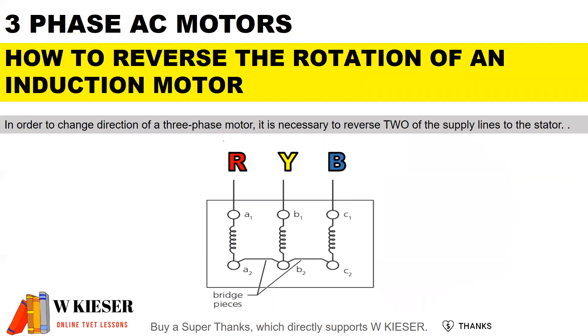How do you reverse the rotation of an AC induction motor? Looking at the terminal box, the three stator windings are connected in star, bridged horizontally. The first line is color coded red, the second stator coil has a line color coded yellow, and the third stator coil has a line color coded blue. In order to change the direction of a three-phase motor, it is necessary to reverse two of the supply lines to the stator — so we simply swap the red wire and the yellow wire to reverse the direction of rotation.